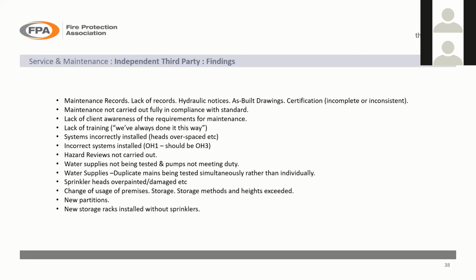And we've been to warehouses where new storage racks are being installed in a fully sprinkled building. They put a couple of new racks in and did not put sprinklers in there as well. Basically, if you get a fire in those, it will overwhelm the rest of the system. And once it's actually started, bear in mind the sprinkler system is there to operate immediately in the event of a fire. If you've got a fully developed fire, it's going to be very, very difficult to guarantee that it would put a well-developed fire out.